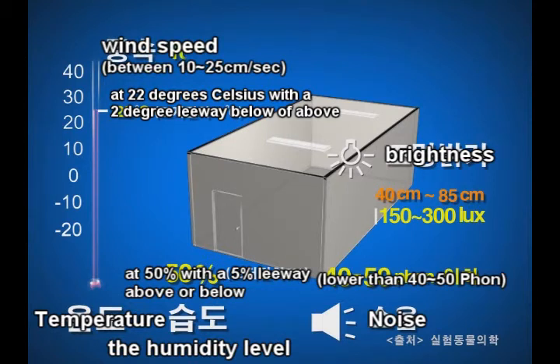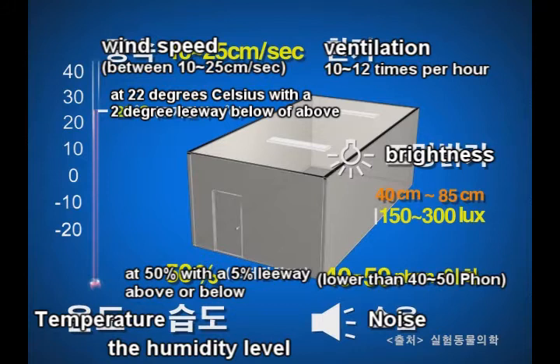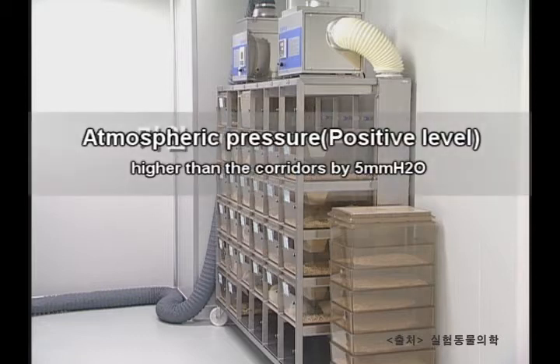Wind speed between 10 to 25 centimeters per second. Ventilation 10 to 12 times per hour. Atmospheric pressure maintained at a level higher than the outside to prevent an inflow of outside air into the room, and especially maintained so that it is also higher than the corridors by 5 millimeters H2O.